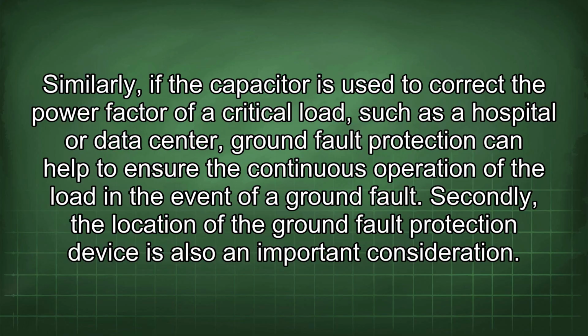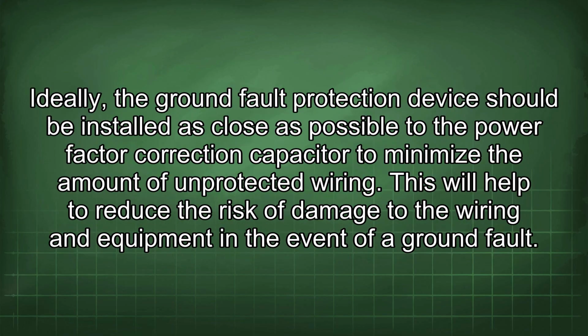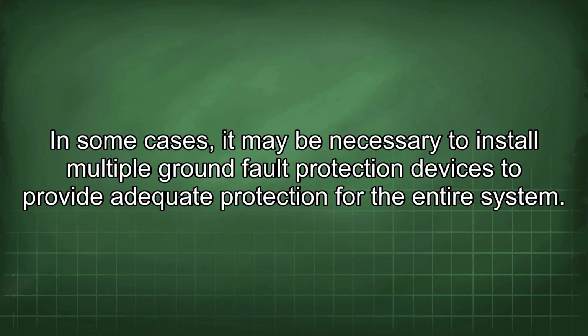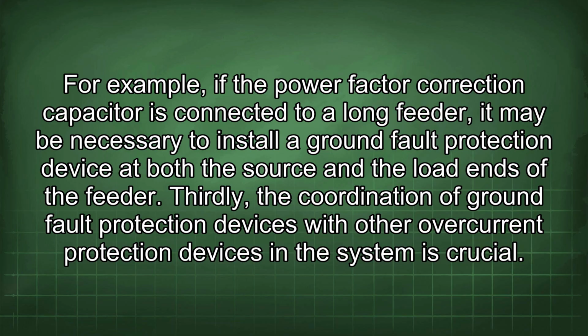Secondly, the location of the ground fault protection device is also an important consideration. Ideally, the ground fault protection device should be installed as close as possible to the power factor correction capacitor to minimize the amount of unprotected wiring. This will help to reduce the risk of damage to the wiring and equipment in the event of a ground fault. In some cases, it may be necessary to install multiple ground fault protection devices to provide adequate protection for the entire system. For example, if the power factor correction capacitor is connected to a long feeder, it may be necessary to install a ground fault protection device at both the source and the load ends of the feeder.